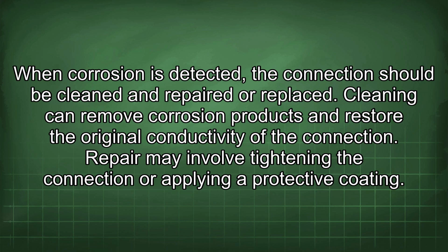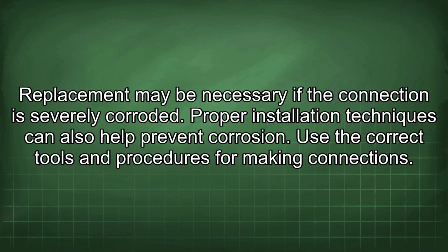When corrosion is detected, the connection should be cleaned and repaired or replaced. Cleaning can remove corrosion products and restore the original conductivity of the connection. Repair may involve tightening the connection or applying a protective coating. Replacement may be necessary if the connection is severely corroded.